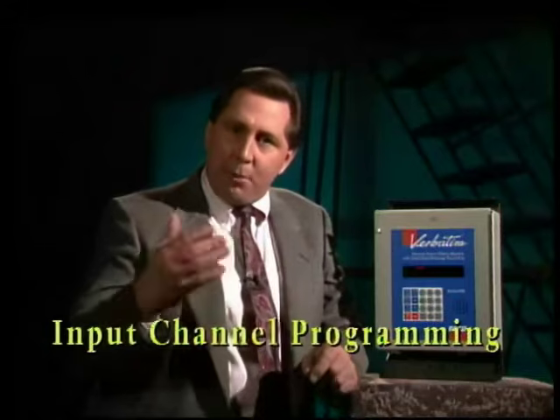Next, you'll need to program the system's input channels. Your Verbatim autodialer needs to know whether its input channels are to be normally closed, that's alarm on open circuit, or normally open, alarm on closed circuit. All contact inputs are initially set normally closed. This is the default setting, and therefore any open circuits, including any inputs left unconnected during installation, will appear as alarms until the inputs are programmed.